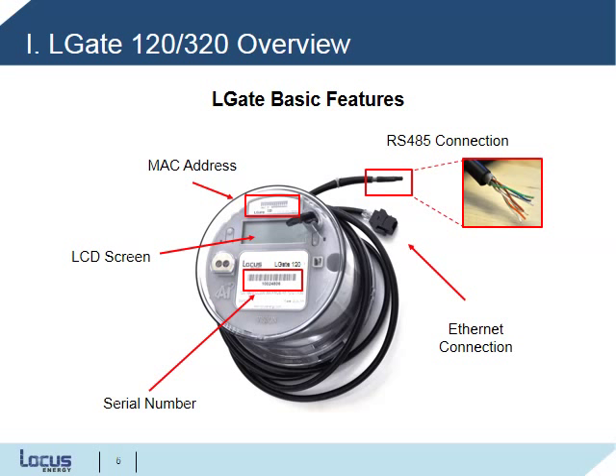Now, as you may have noticed, the LGate 120 and 320 look very similar. This is because these meters share the same internal data logger, cellular modem, and meter housing, so the same basic features and functionality for these meters are the same. The cell modem is inside the LGate socket meter. The LCD screen, front and center, displays instantaneous power, voltage, and amperage readings for easy on-site installation verification. The MAC address is printed above the LCD screen, and the power meter serial number is printed just below.